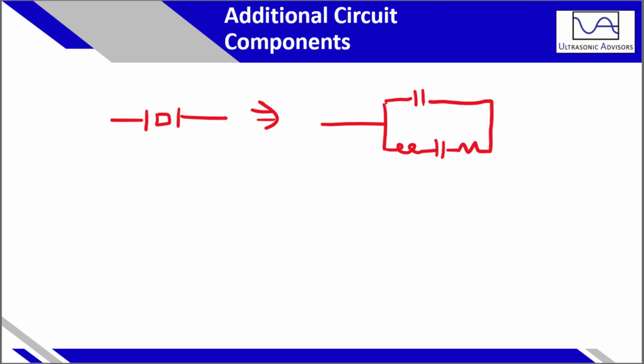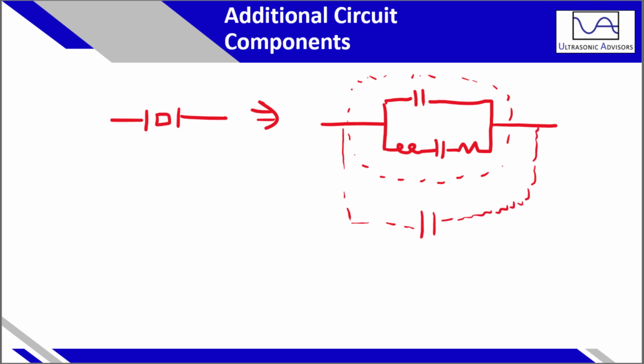response. So we have our piezo crystal, which obviously, we spoke about how it equates to the LCR circuit in parallel with a capacitor. But in this case, what happened was we assumed that this is the piezo here, and the calibration procedure assumes that there is a probe or a cable parallel capacitance that's added from the cable that's going back to do the measurement, the 2 terminals or 4 terminals. So it creates a capacitance in between these 2 leads.